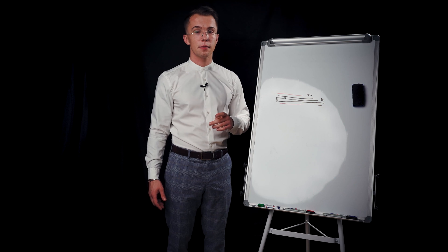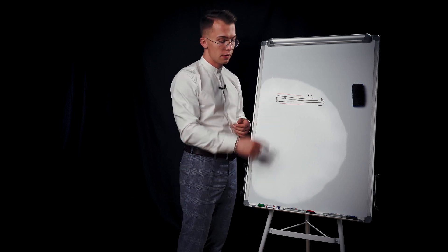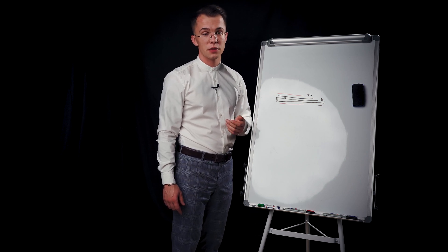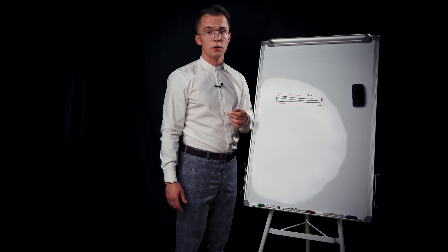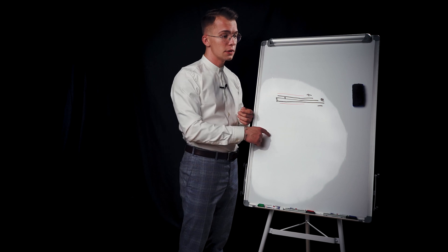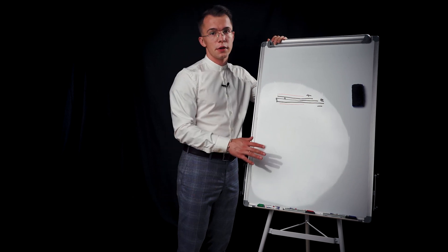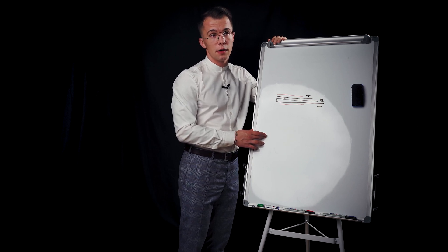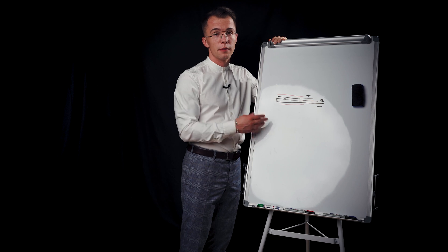The first step is to eliminate the easiest problems to find, which is the fuse spur. To eliminate the fuse spur, you probably want to replace it, which is quite easy if you have the qualifications. If not, you might want to ask an electrician, or it might be worth powering down the system, leaving it on batteries, and seeing if the earth fault remains. Your meter in this case will be the panel itself, as it indicates if you've found the fault or not. You're not going to be using a multimeter because the best measuring device will be the fire alarm panel itself.